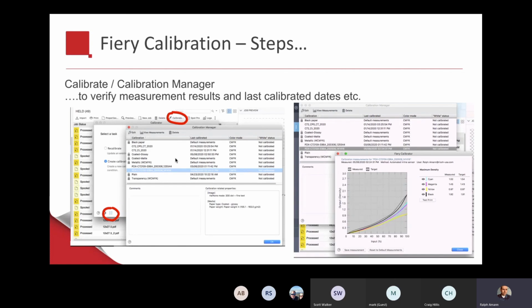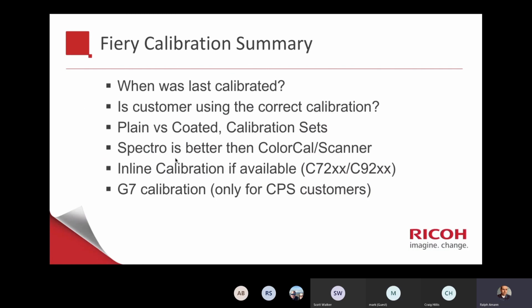Last one on calibration: when you hit that calibrate button, you can go to those 3 little lines at the bottom left, and that opens up the calibration manager. There you can see all the named calibration sets and when they were last calibrated. You can even click on one and see the measurements again on the right side. So, summary on calibration: always find out when it was last calibrated.